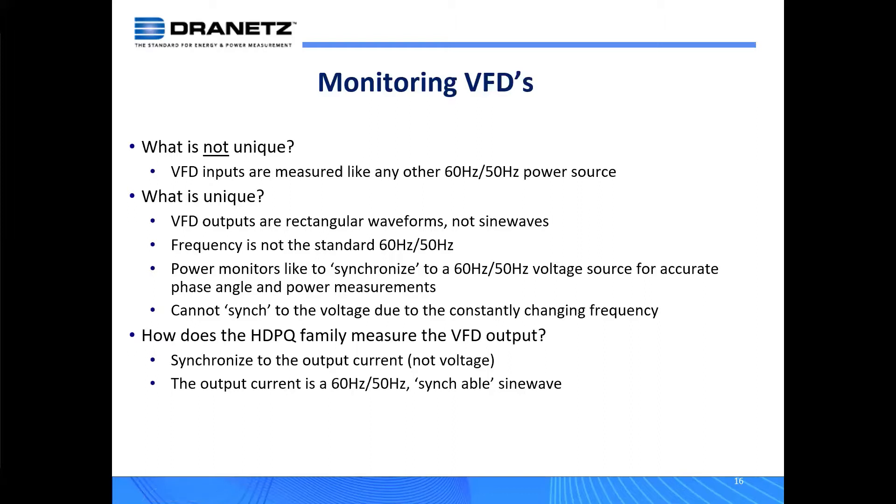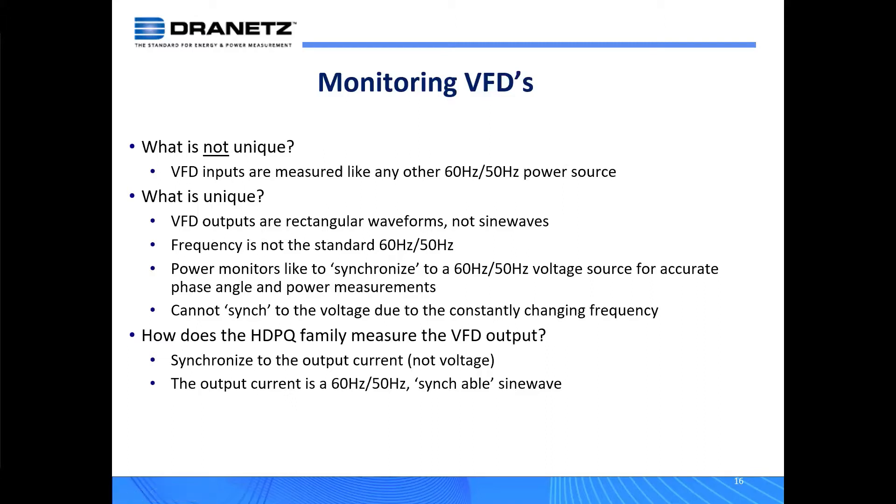It's the output of the VFD. What's unique about that output is that it's a rectangular waveform, not a sine wave, and the frequency is not that standard 60 hertz or 50 hertz. Power monitors like to synchronize to a signal, usually 50 or 60 hertz, because it helps to get accurate phase angle and relationship measurements between the voltage channels and between voltage and current for power factor and watts and VAs. When that frequency is changing dynamically, it's hard to do that because the frequency of the voltage is not related to the frequency of the current anymore.